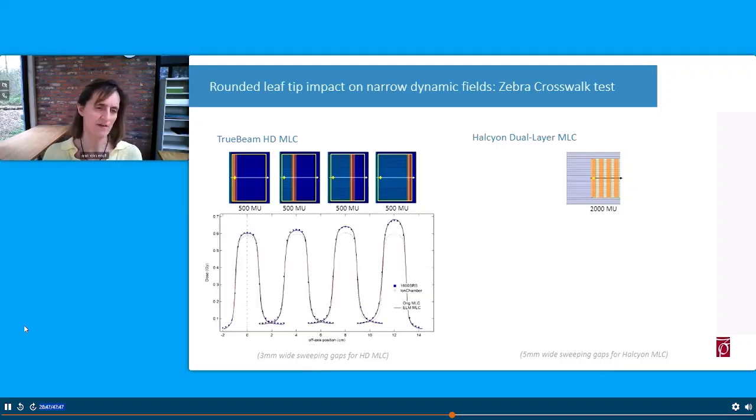They are very consistent. The central zebra stripe, for that one we have about 3% difference on the dose on the beam axis. This could still be considered a clinically acceptable deviation, I think. But as we move further and further off axis, the discrepancies really increase, I think, up to 15% for the 12 centimeter off axis stripe when using the old model.